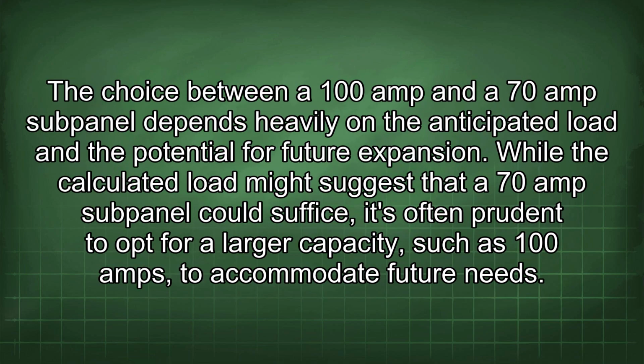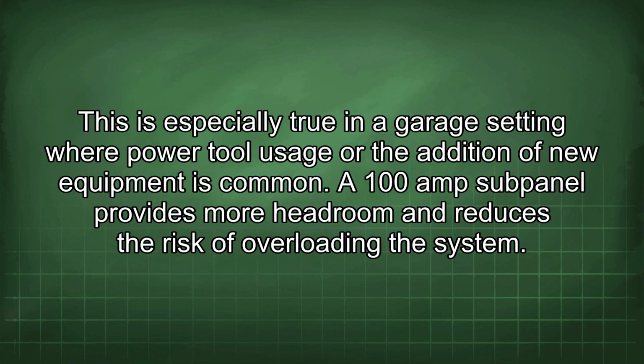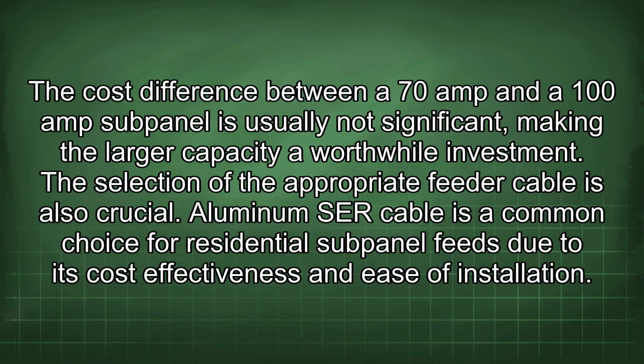The choice between a 100 amp and a 70 amp subpanel depends heavily on the anticipated load and the potential for future expansion. While the calculated load might suggest that a 70 amp subpanel could suffice, it's often prudent to opt for a larger capacity, such as 100 amps, to accommodate future needs. This is especially true in a garage setting where power tool usage or the addition of new equipment is common. A 100 amp subpanel provides more headroom and reduces the risk of overloading the system. The cost difference between a 70 amp and a 100 amp subpanel is usually not significant, making the larger capacity a worthwhile investment. The selection of the appropriate feeder cable is also crucial.